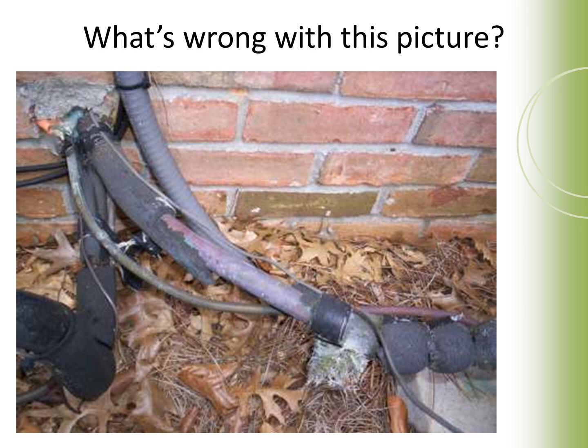If you look closely here, you can see that the insulation is worn off of the refrigerant pipes that go from the inside evaporating unit to the outside condensing unit. This can result in freezing of these pipes, and it looks like there might also be some leaks around this. This is definitely time to get checked out by a mechanical technician.